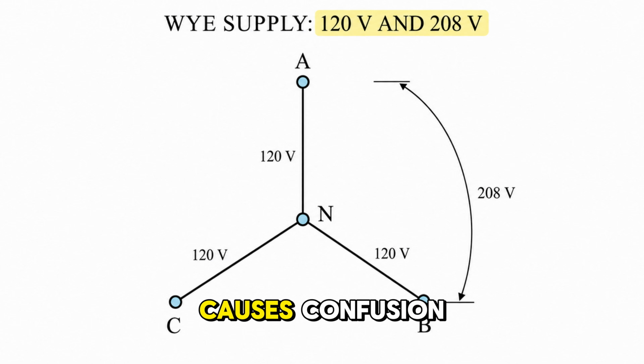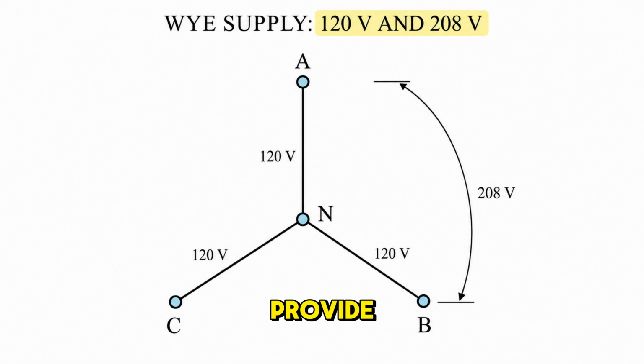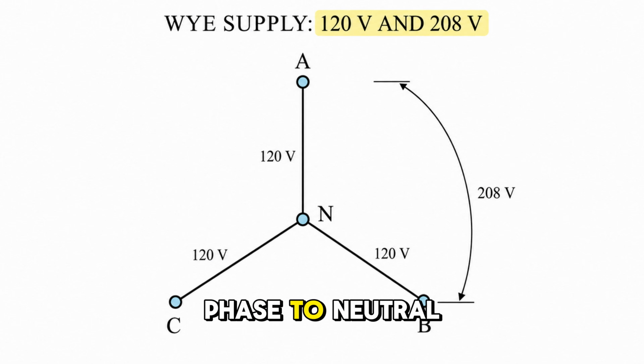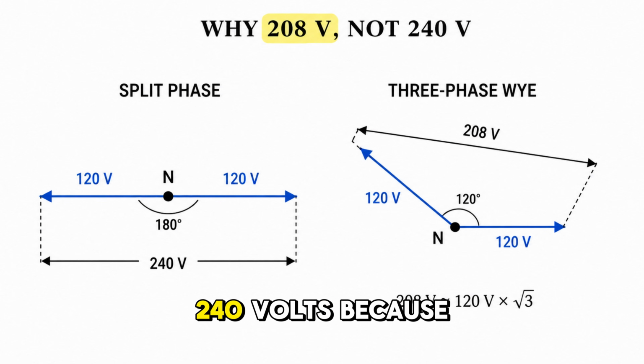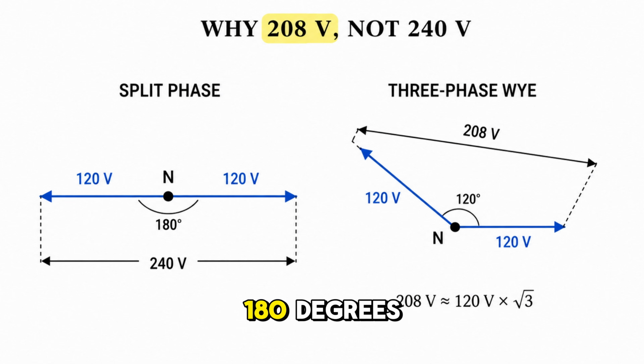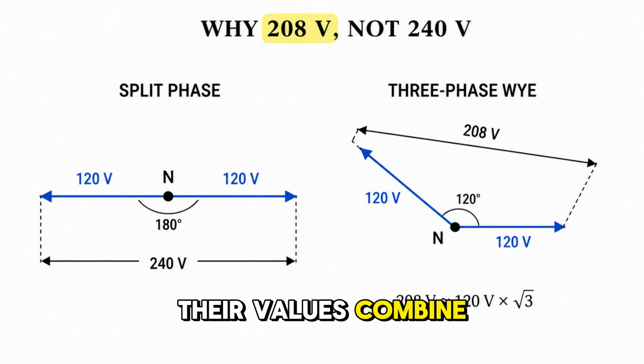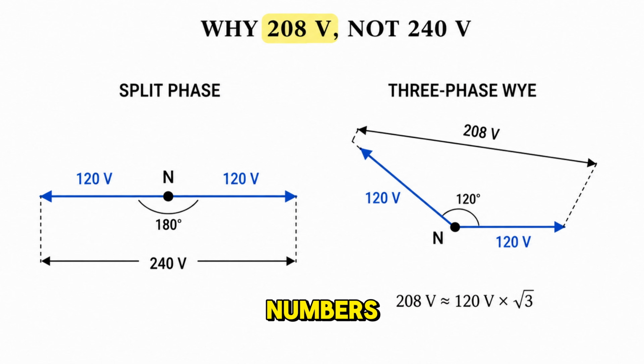Another detail often causes confusion. A common three-phase Y system can provide 120 volts from any phase to neutral, yet it provides 208 volts between two phases. The result is not 240 volts because the two-phase voltages are separated by 120 degrees instead of 180 degrees. Their values combine as vectors rather than ordinary numbers.